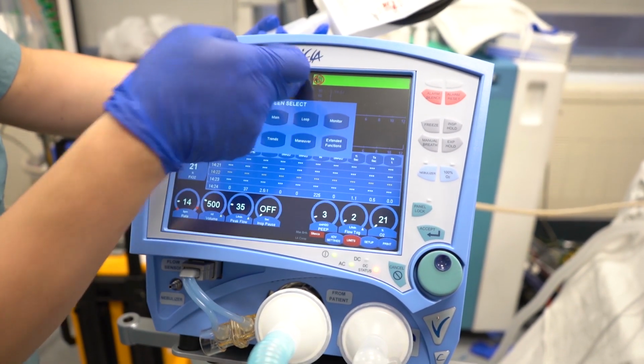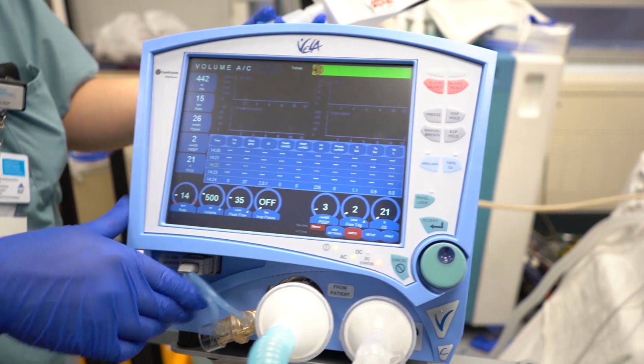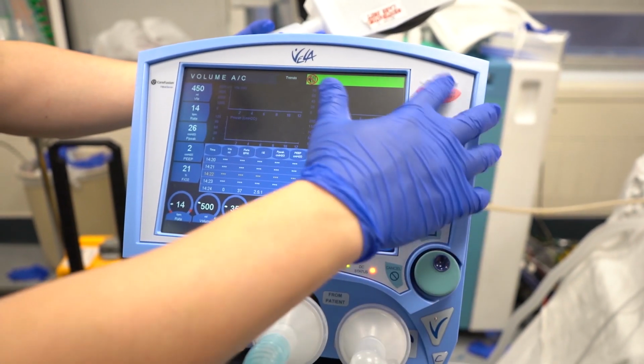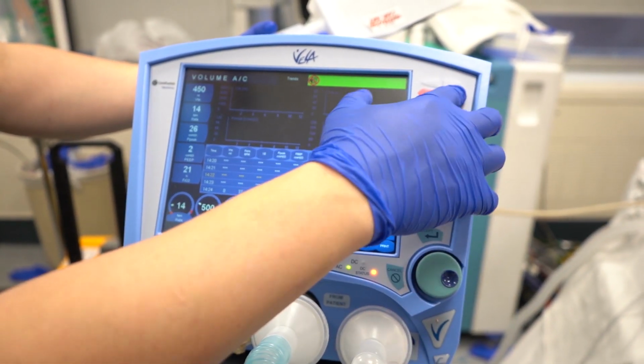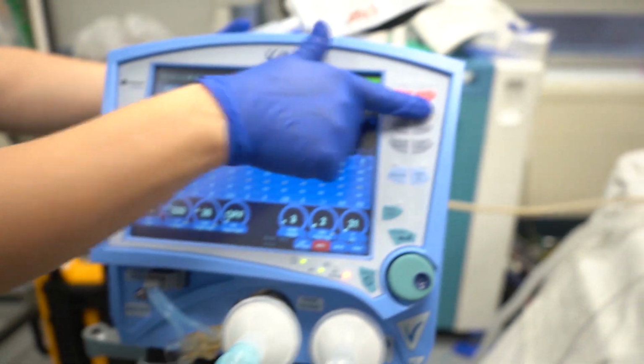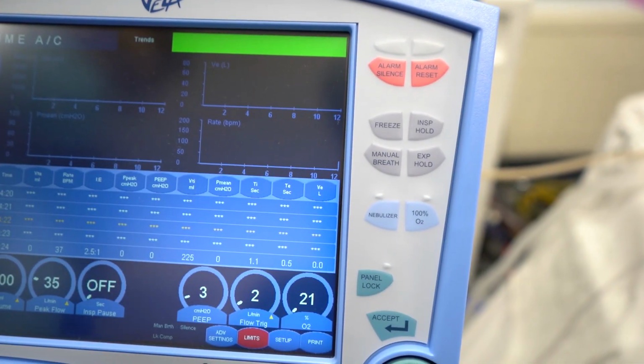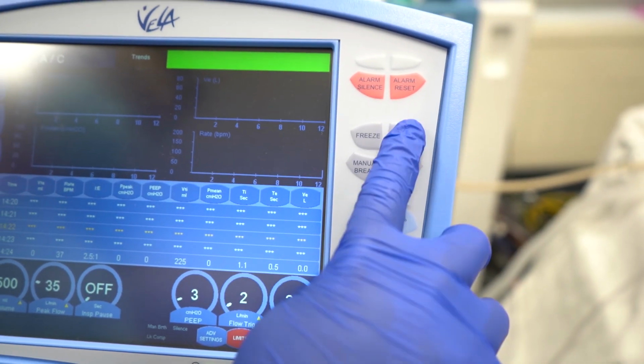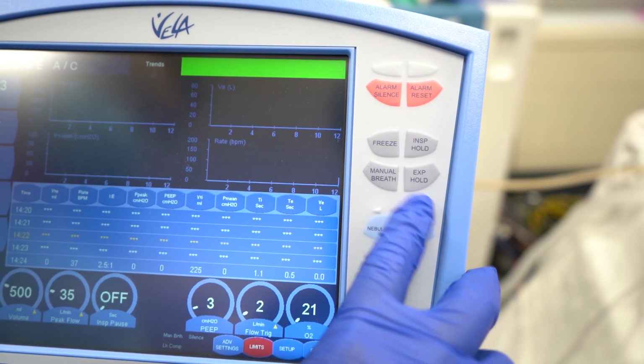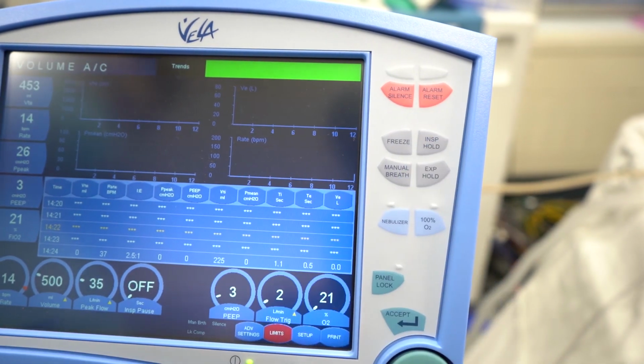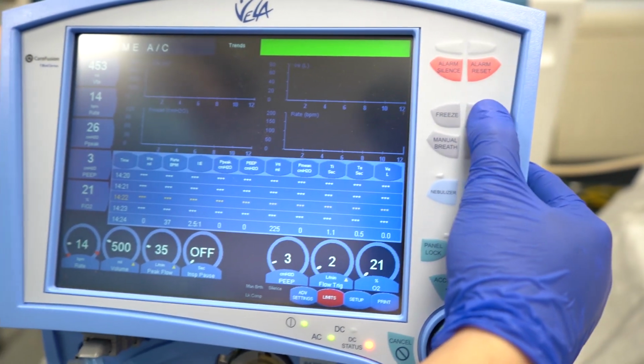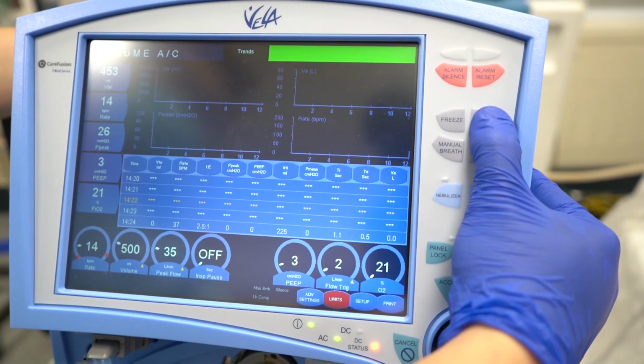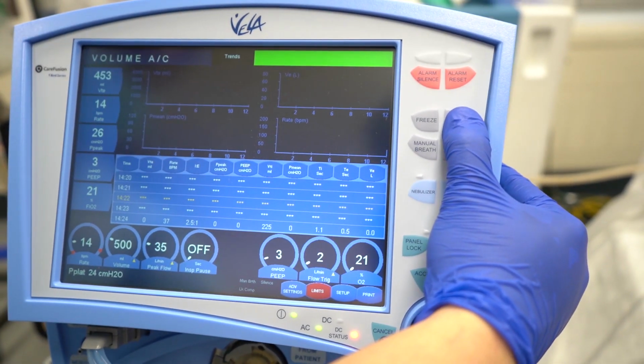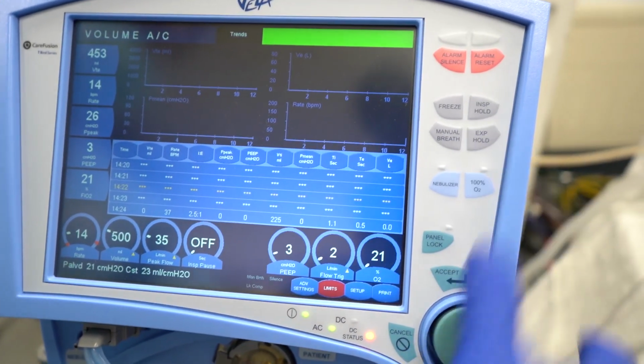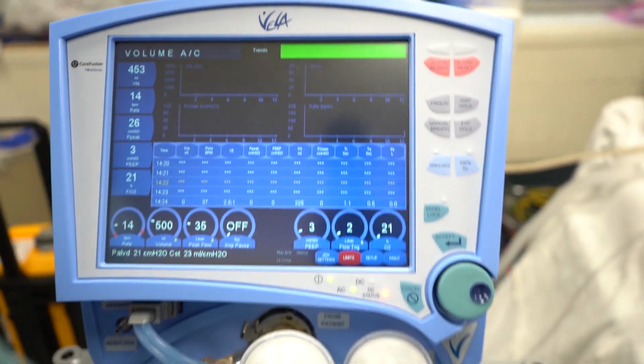But those are some of the basic functions, simply how to turn it on, to troubleshoot, or some of the functions on the side. Your alarm reset and alarm silence are the two red buttons on the top. To get a plateau pressure, inspiratory hold is on the right hand side here. So you're going to press that, and then down towards the left hand side, that's where your readings will populate. So your plateau, and then after that you'll see your resistance and compliance.